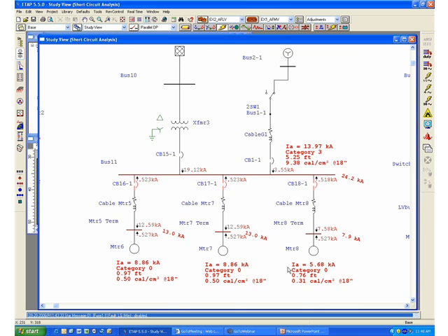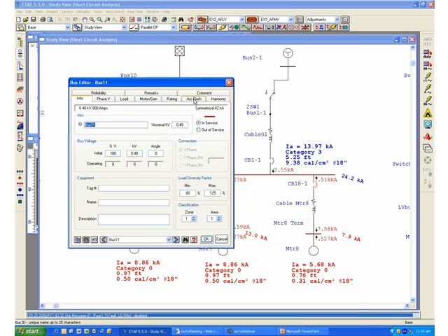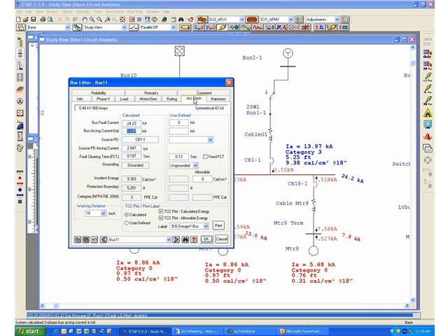Of particular importance in this system is to understand how the program will also determine the grounding of the system. If you double-click on bus 11, which is the main bus for this system, and we go to the arc flash page, we'll be able to see that for this particular case, the program has determined the system to be grounded.